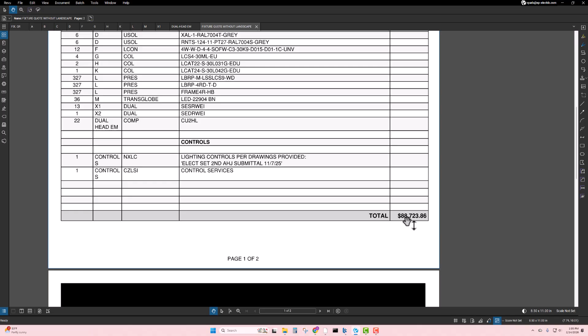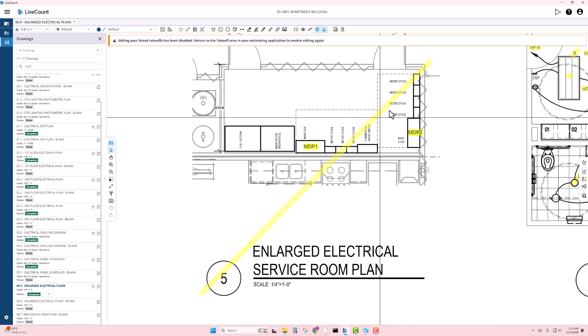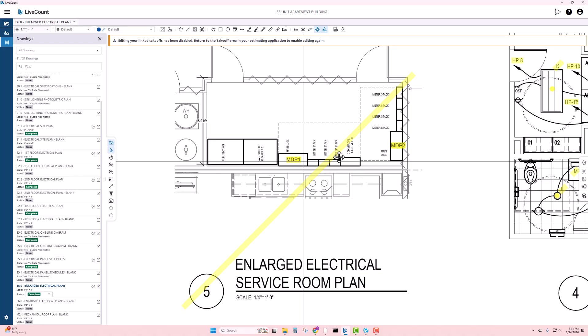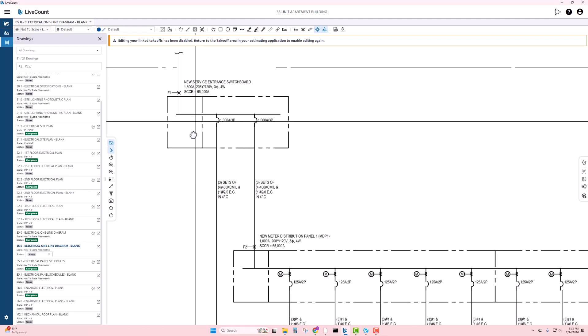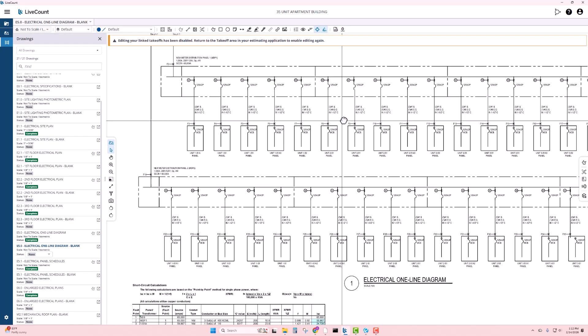Switchgear. When you're ready to start counting switchgear, you're going to want to locate your one-line diagram, typically, and then you're going to want to locate a layout for your electrical room. So in this case, we have an electrical room on the first floor. You've got MDP1, MDP2, these are meter stacks. Then you've got a main switchgear here. You can see this is the new service entrance switchboard. That's right here. And then we have a 1,000 amp board with meter packs, and then another 1,000 amp meter board with meter packs.